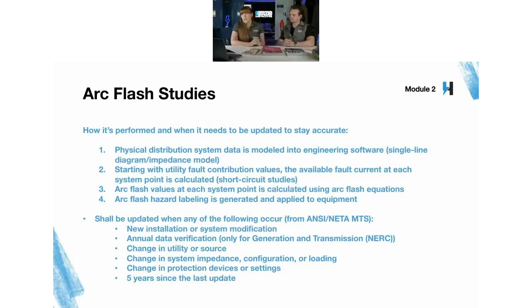John asked a good question, and I think this is a good time to go ahead and answer it. Has there been a time where the local power company updated their equipment to increase fault current levels and let people know? Did you get a heads up? Well, no. Yes, actually, that's twofold, two questions, right? So yes, things change in the utility contribution all the time, especially because we're connected in a grid. So maybe the utility company has changed their operation, their means of power distribution, right? And that can, of course, change the amount of available fault current at your facility. Utilities are adding and removing customers all the time. That's the other point. So the load they're delivering will affect their contribution to your system, whether you know it or not. Whether you make a change to your system at all, the utility is always making changes.